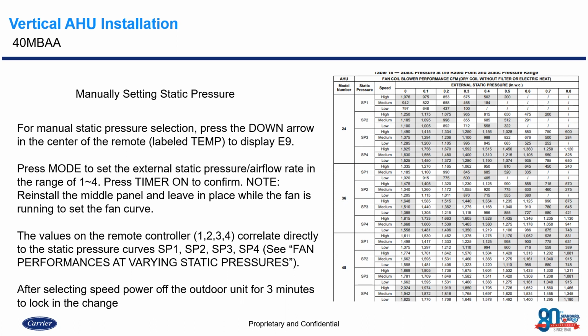Okay. So you have 2 options: automatic airflow, or manually setting the static pressure. You want to try out automatic airflow? Be my guest, absolutely try it. If it doesn't seem to work out, or it's just not what you thought it would be, you can always go back and manually set that static pressure. But that's something that we need to do on every install, whether we're dealing with a 40 MBAA or a 40 MBDQ, which is the horizontal ducted units, which most of you, if not all, should be familiar with by now.